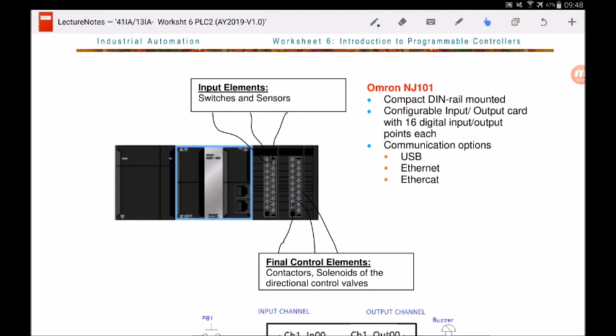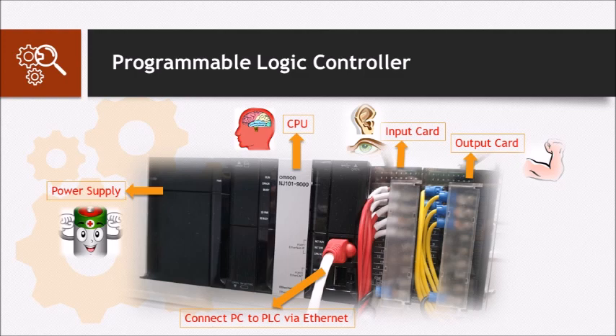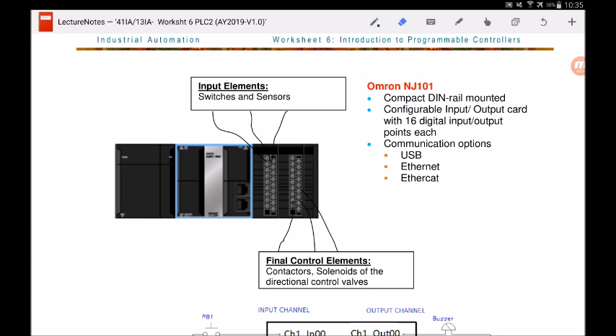We will now learn about PLCs and how to use them in the control chain. The PLC model we are going to use in the lab is the OMRON NJ101 series. We will teach programming instructions based on this model, which follows the industry standard IEC 61131-3. The OMRON NJ101 PLC has a power supply, CPU, input card, and output card. The input card is where you connect input elements such as sensors and switches, and the output card is where you connect the final control elements and output elements.